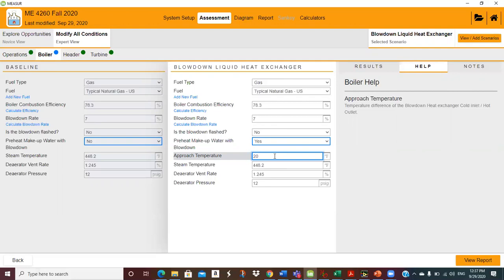It's just a matter of getting more surface area to transfer heat across a metal wall — that's all we're doing in a heat exchanger. I use 20 degrees approach because the old SSAT program used to default to that. It could be 5, 10, 15, or 20 — probably not a whole lot bigger than 20 or 25. You've got such a big temperature difference that you ought to be able to cool down that 400-something-degree water. This says the blowdown stream is going to leave at 90 degrees.